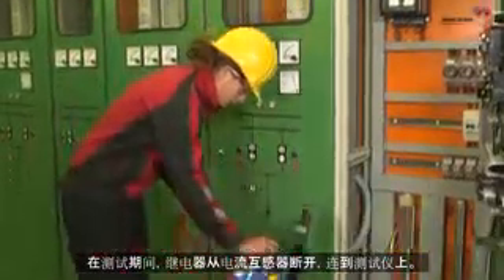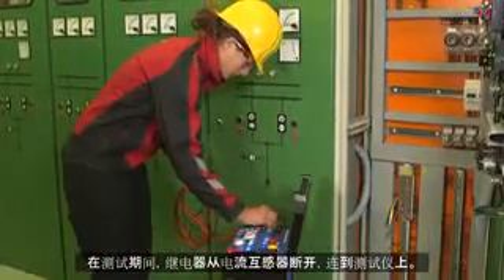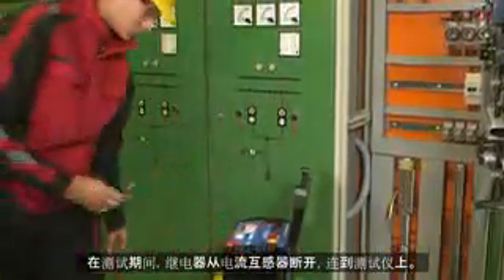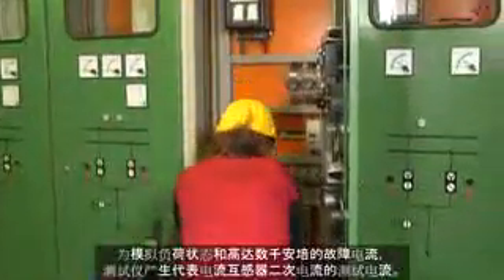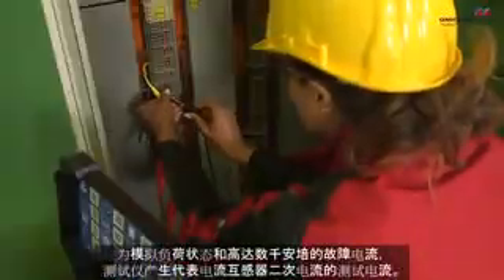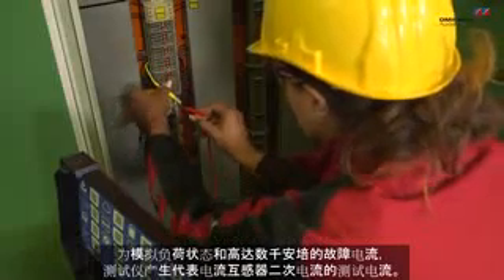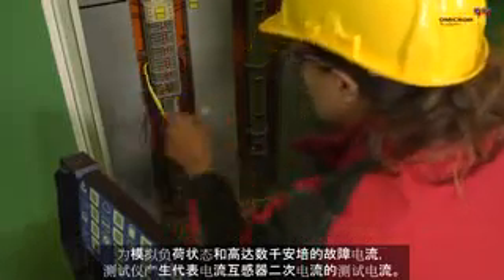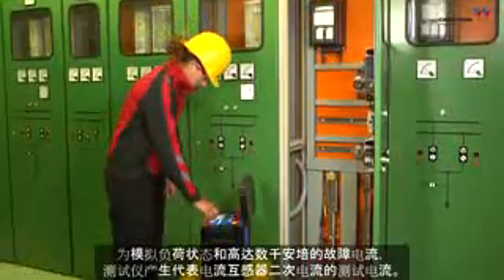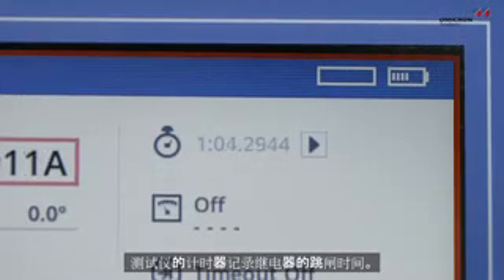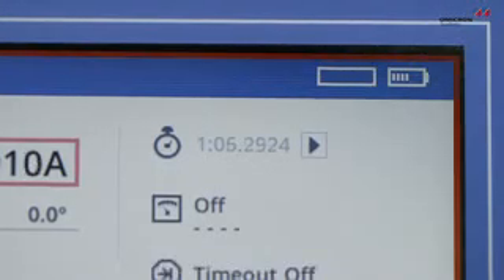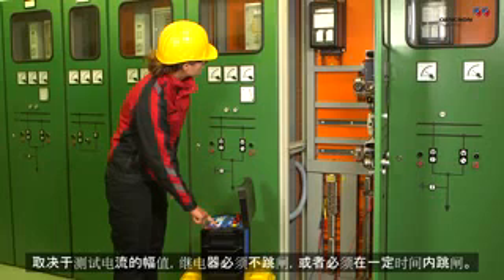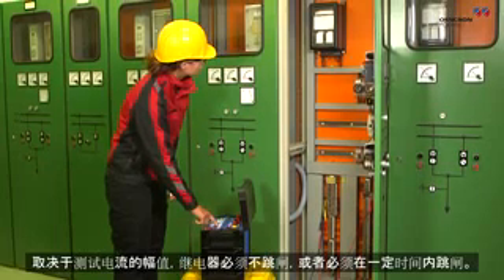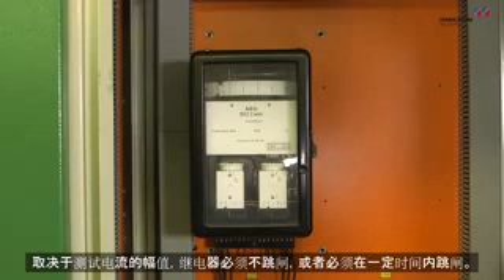During testing, a relay is disconnected from the current transformer and connected to a test set instead. In order to simulate load conditions and fault currents of up to a few thousand amps, the test set generates a current that represents the secondary current of the current transformer. The test set timer records the relay's trip time. Depending on the magnitude of the test current, the relay must not trip, or it has to trip within a certain time.